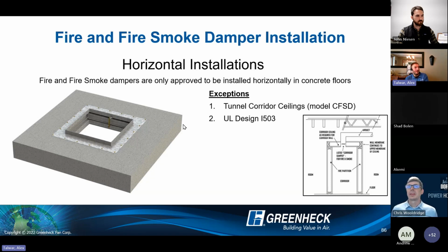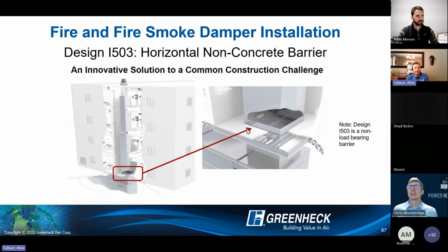But anything else that's fire rated that's going to be horizontal is going to either have to be in concrete or this UL design I-503. And that's something we came out with. Actually, happy to say I was in the test lab when we were pioneering that one, but 2019, I believe, was when we came out with that. It allows a way for a fire or fire smoke damper to be mounted in the horizontal position in something other than concrete. Basically, there was really nothing until this construction came along. So outside of that, there aren't a lot of options for horizontal mounting of fire or fire smoke dampers. So those are pretty much your options there.